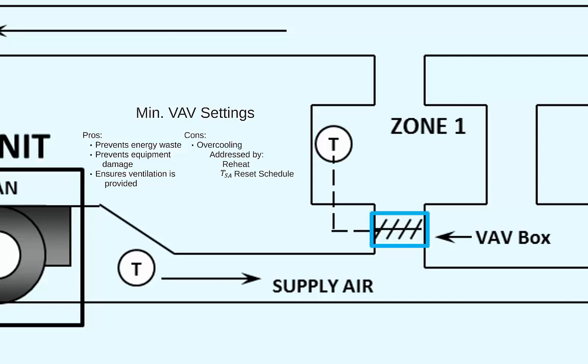overcooling the space. If the controller is telling the damper to close since the space temperature is dropping, but the damper is at a minimum position, more cold air will be sent to the space than required. Thus, the room air temperature will drop somewhere below set point.